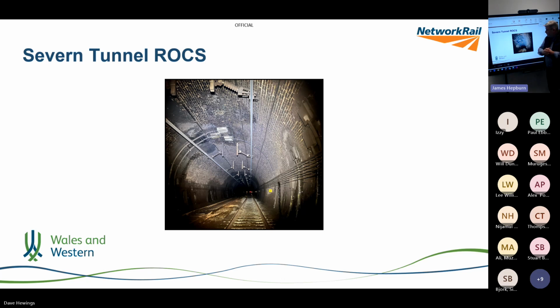And actually, the aluminium contact wire was a good move at the time to allow that corrosion to be removed, to allow a wider study piece of work to be put in place to understand what the long-term answer would be. So 2018, the whole thing was replaced. The beam was replaced in sections where it had corroded. The rest of it was left there, but the full contact wire was removed and replaced with a new aluminium contact wire, accepting it probably wouldn't last the life of a copper contact wire. And that got us to the point of electric services in 2019 between Wales and England for the first time. So from our point of view, a success, but of course, some issues to deal with.